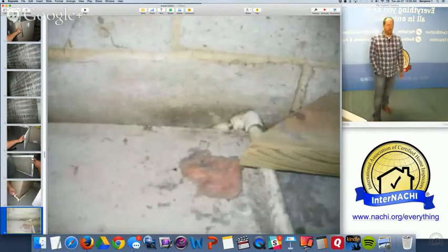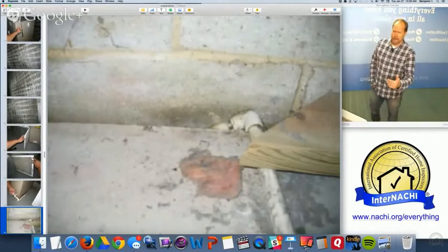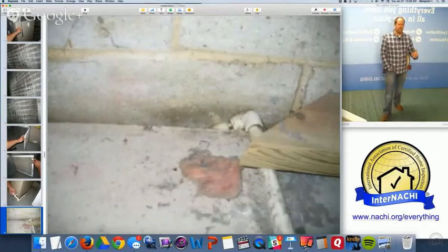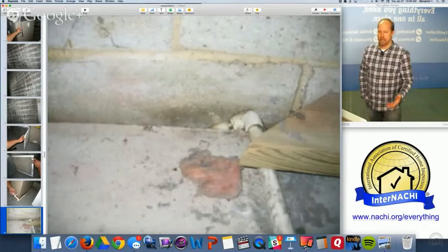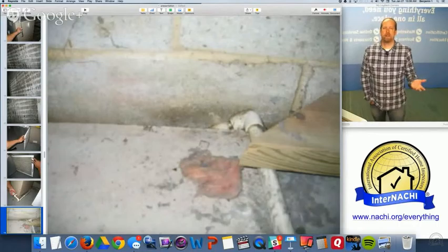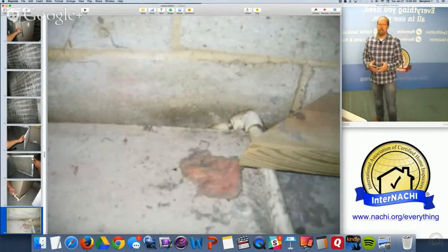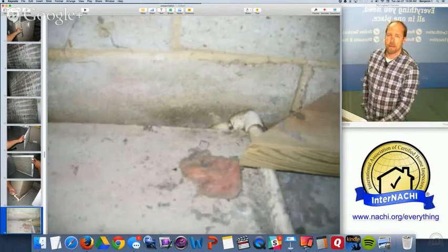So this is a basement with a floating slab on gravel, and there's a space between the outer edge of the slab floor and the foundation wall. A lot of builders just dump the condensate right there, not realizing that it's not going away. They're just adding gallons of water in a concentrated area in the basement and hoping that it drains or evaporates away. Not sure.